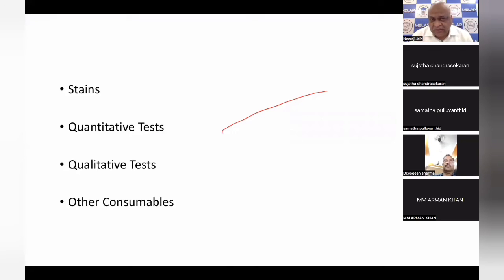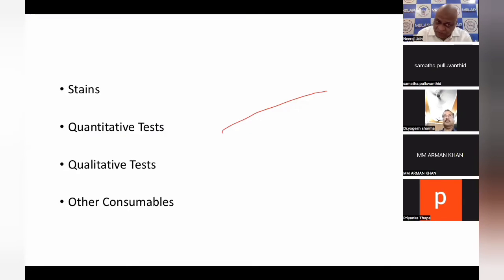We use different terms for this: lot acceptance testing, lot validation, lot verification, kit validation, kit verification. Whatever term you are using, that is your decision. But the standard term is lot acceptance testing, to ensure this particular lot is acceptable to you. And remember one thing: if you are receiving 4 kits of the same lot at one time, in one shipment, then you have to carry out lot acceptance testing only once. If you are receiving in the same shipment 2 kits of one lot and 2 kits of another lot, then you have to carry out lot acceptance testing for both the lots.